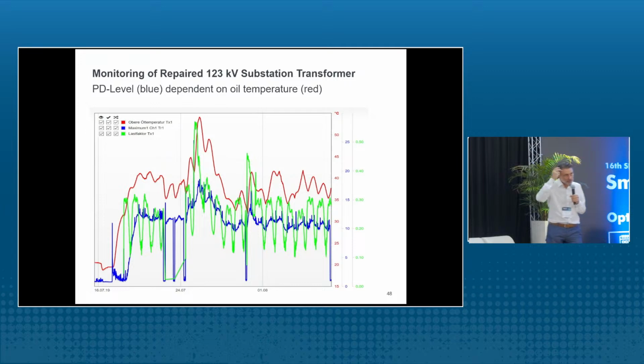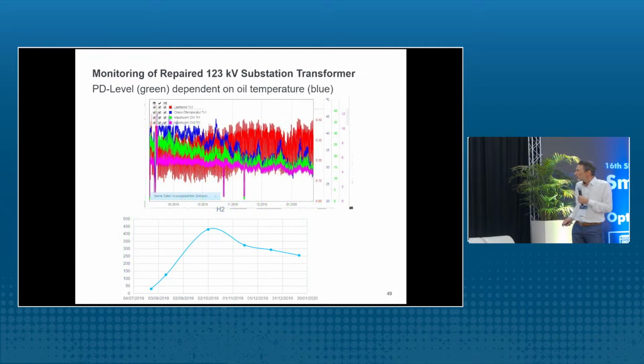Why is it dependent on temperature? If the transformer is warmer, then the oil flow through the winding is higher because it's a natural cooled transformer. And if you have more oil flow, then of course you have also more flow of particles, which create these PD. You cannot see this without monitoring. I think this is one of the first examples which shows the behavior of PD dependent on temperature of the transformer.